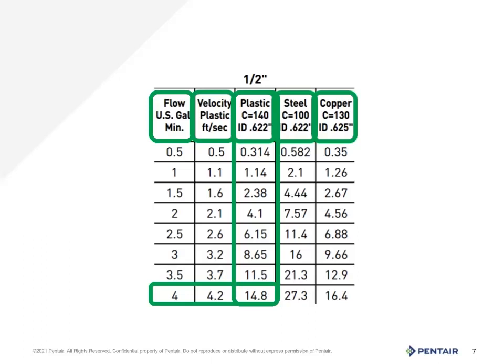Remember, on the suction side we strive to remain under five feet per second, and on the discharge we try to keep it under seven feet per second ideally. And finally, the friction loss, which in this case is expressed in feet of head for plastic. In this example, we see that the loss is 14.8 feet of head per 100 feet, as the chart was based upon 100 foot lengths. A quick point to remember: if you divide 14.8 by the magic number 2.31, you'll get the pressure loss, which is 6.4 PSI.